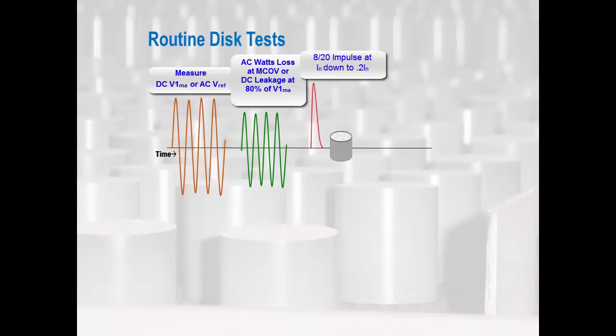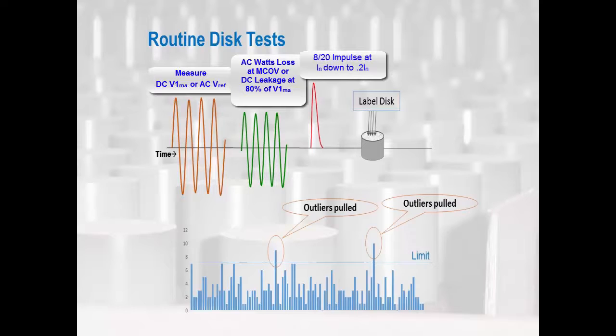The third step is an impulse at a current between 0.2 and 2 times the nominal current of the disk. This is a crucial test. From this test, a good quality supplier can guarantee their published discharge voltages. Once the AC and impulse tests are completed, the disk can be categorized and labeled. This information is necessary for arrestor assembly. If the characteristics are not within the max or min limits of the disk, they are pulled from the inventory and not used. The data can also be used to assist in the fabrication process control. If a characteristic is running near its limit, many options in process adjustment are available to the good quality supplier.